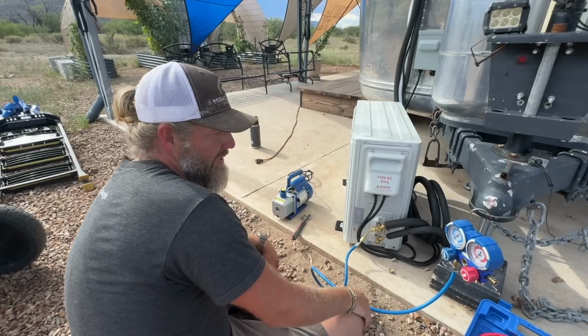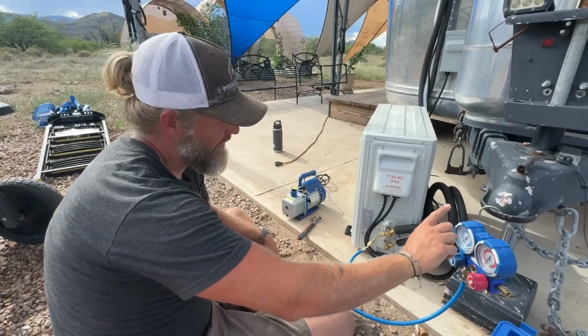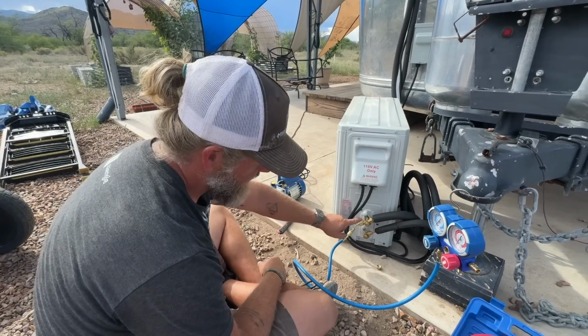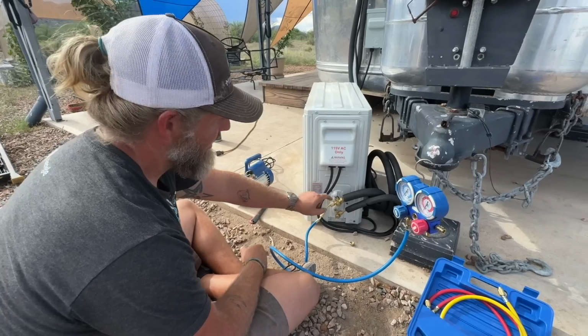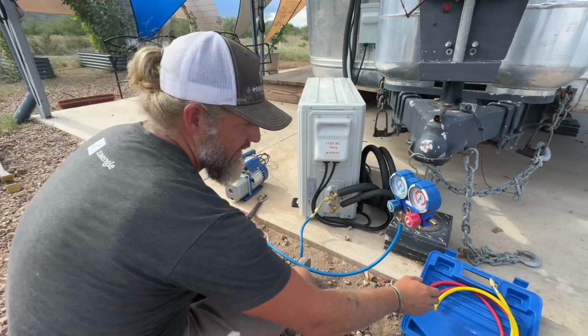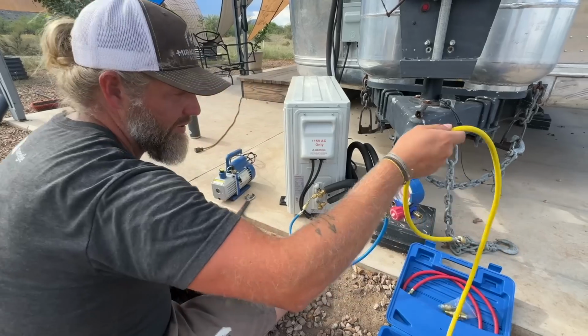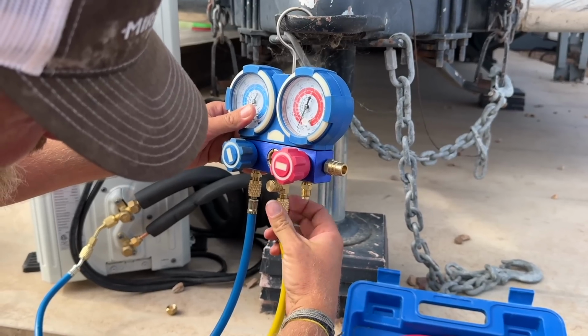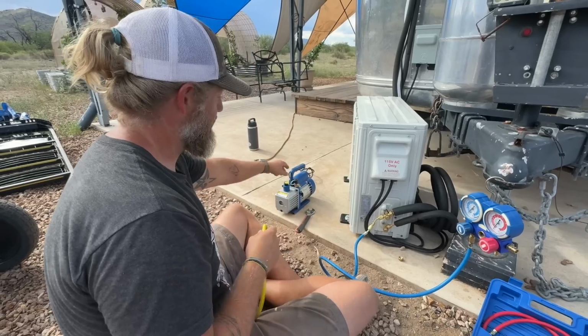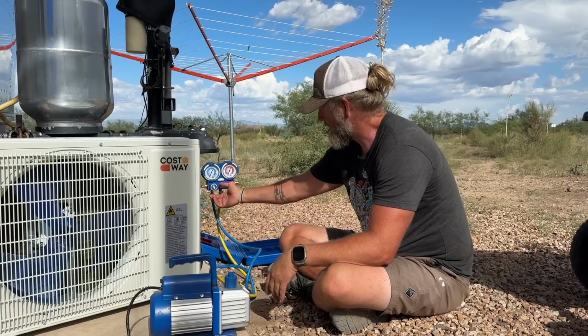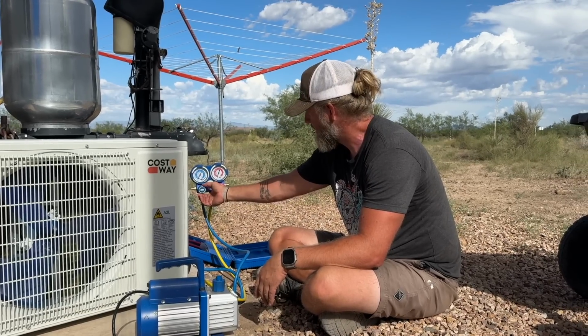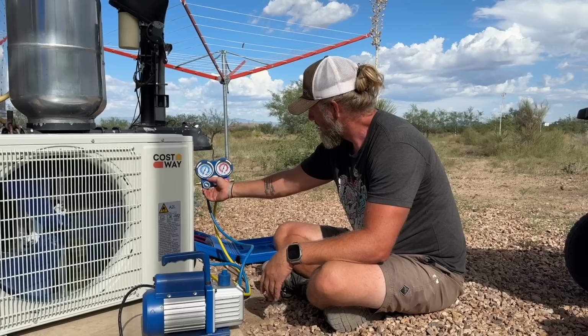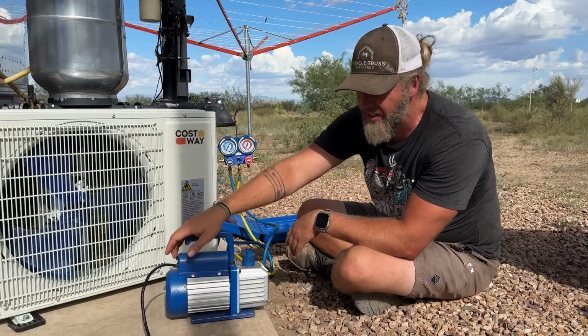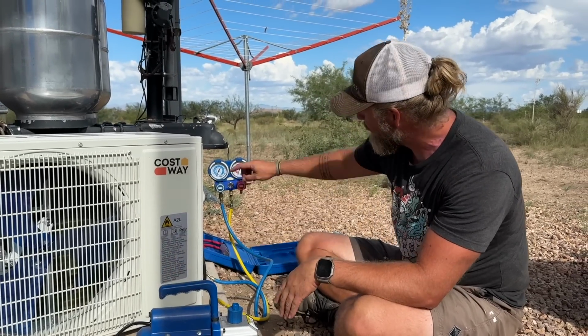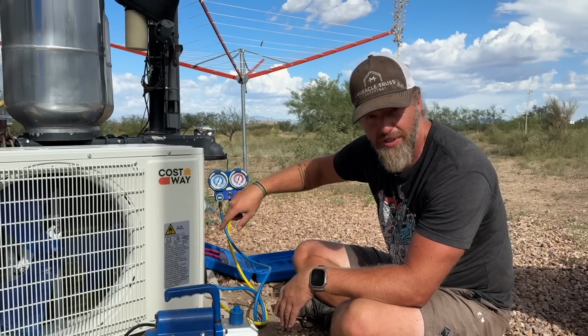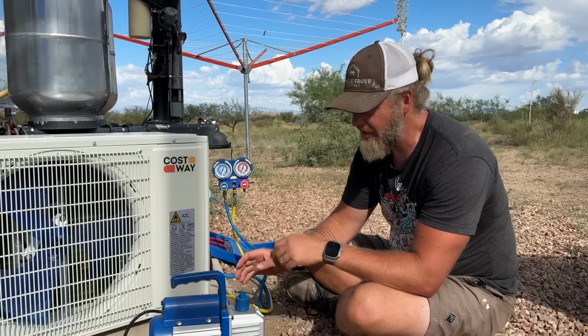The first step is to go from the blue side of the manifold into the large diameter gas line. Then we take the yellow hose and go from the middle of the manifold into the vacuum pump. We open the blue gauge all the way, then turn the vacuum pump on. We wait 15 minutes, hopefully it will draw down to a negative pressure, and then we'll move to the next step.